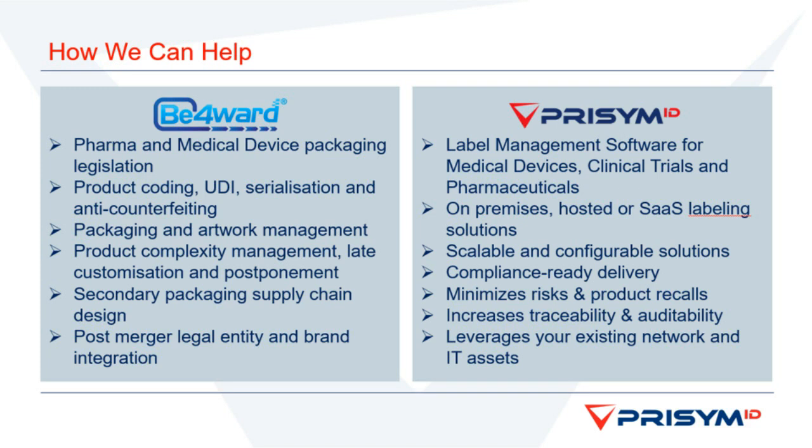For investigational only items, there will be a new text that has to go onto those labels, which identifies that this is exclusively for clinical investigation. And this has translation implications as well. There's some additional information for residual risks. So for pregnant women or other such vulnerable groups, there's additional information that's going to be required on those labels.